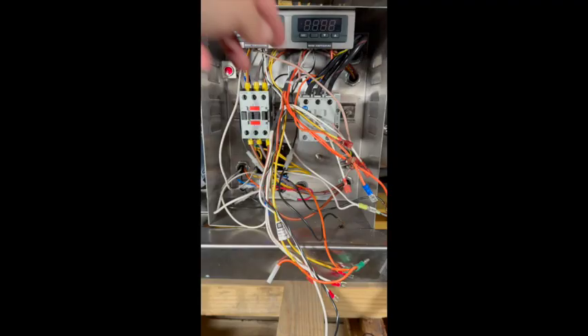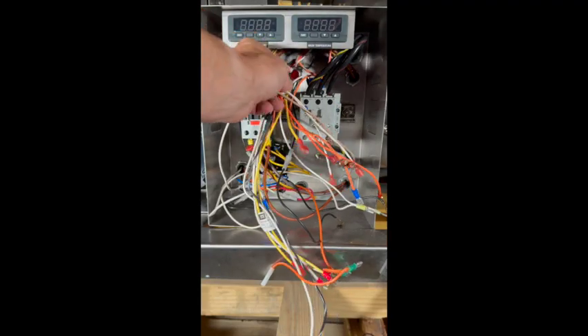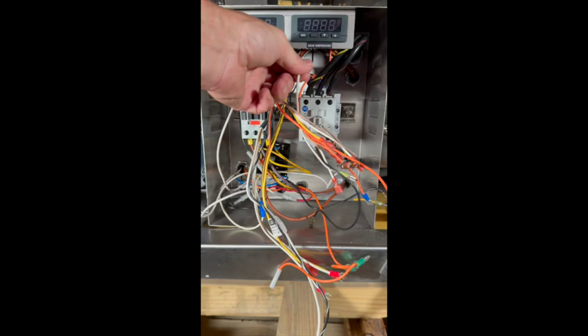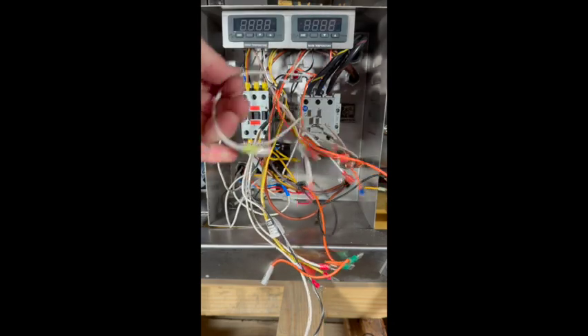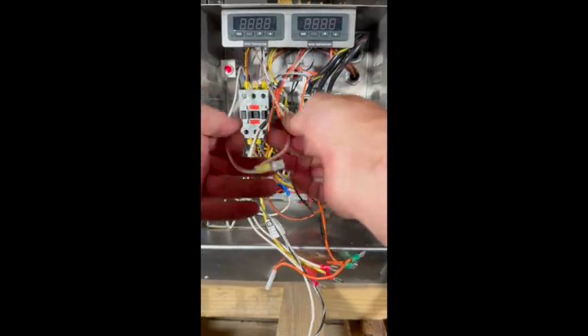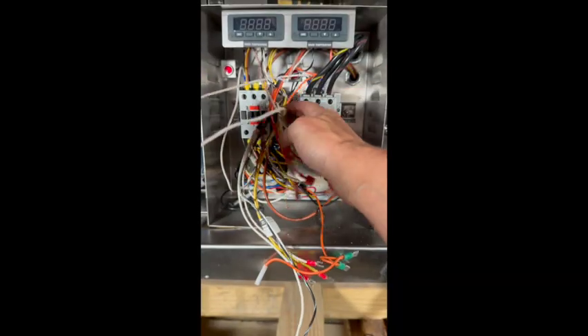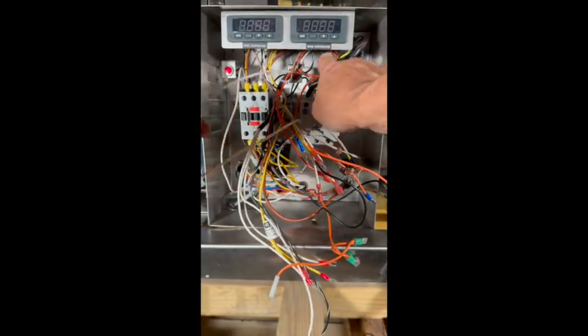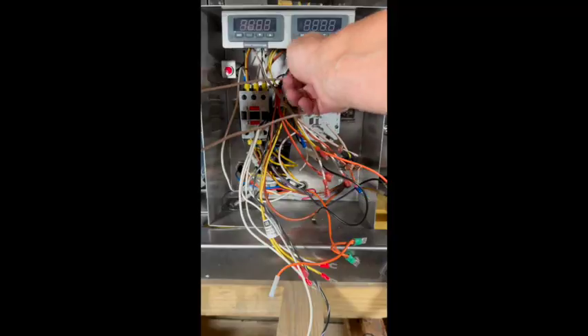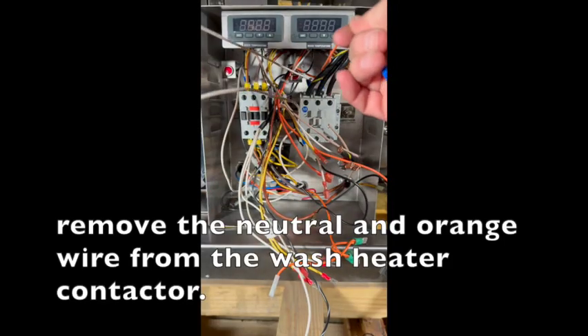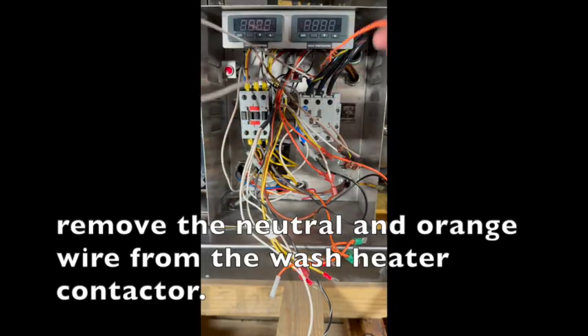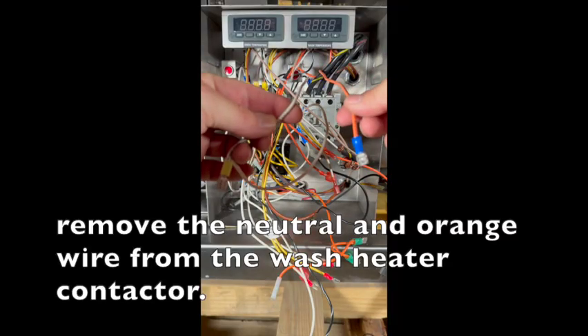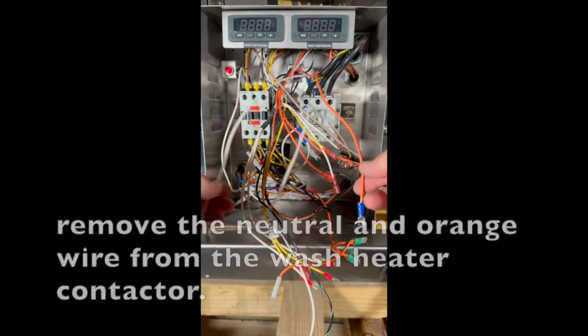After the delay relay has been removed, we can go ahead and remove the old wires connecting the contactor coil. So A1 and A2 is going to be a white, neutral, and an orange. We can remove those from the contactor. On the 60 amp, they're both on top.